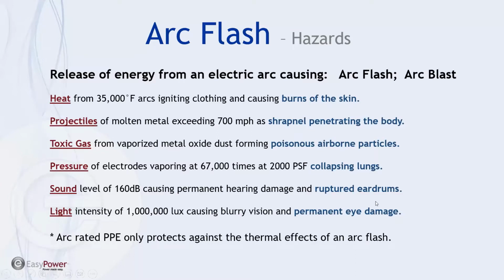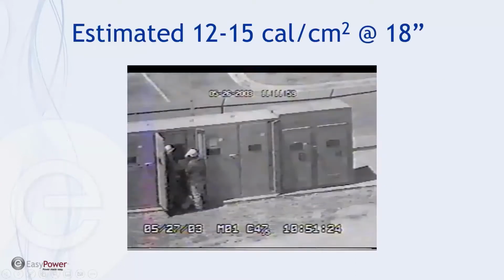And one of the things I like to start with is an accident report from OSHA that I found on the OSHA website and was captured in a CCTV frame from the original event. So I'm reading here directly from the accident report. A crew of electricians and facility personnel for a Wisconsin meatpacking plant had completed an annual cleaning of electrical utilization substations 1 and 2. To facilitate cleaning, the plant was switched from outside utility power to emergency generators, and after the substations were cleaned, the process to switch back to utility power was started, and they had a problem with the transfer switch that was inside this particular cabinet.